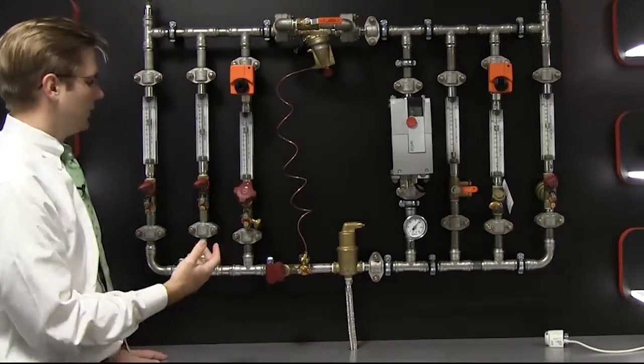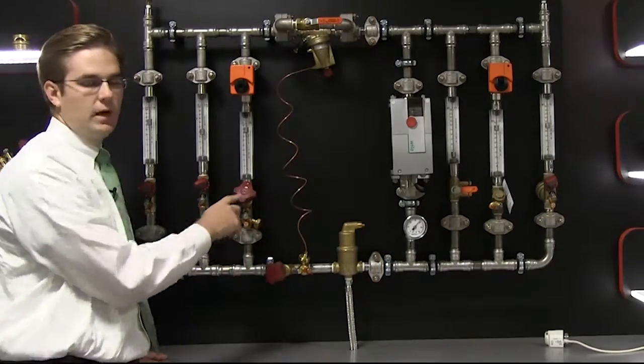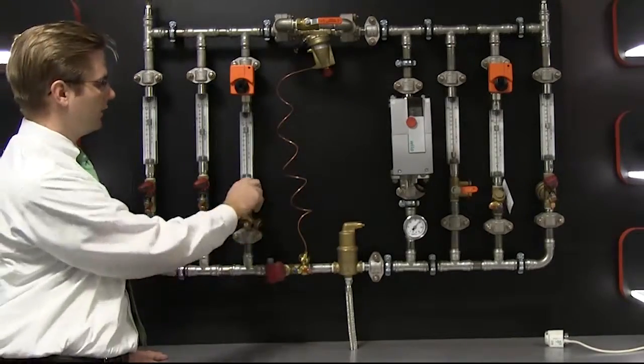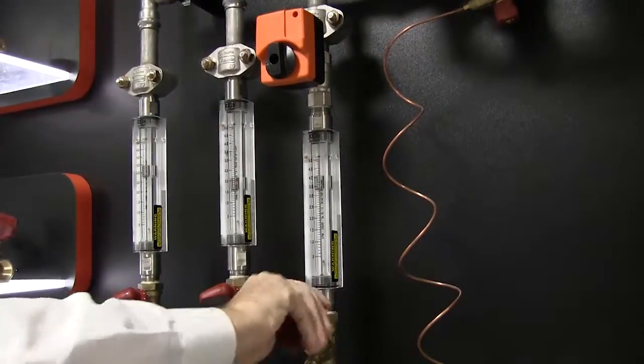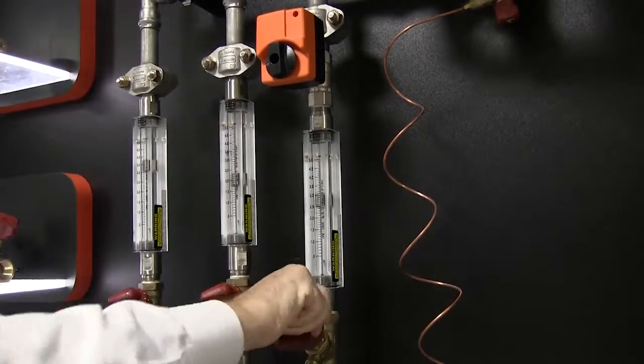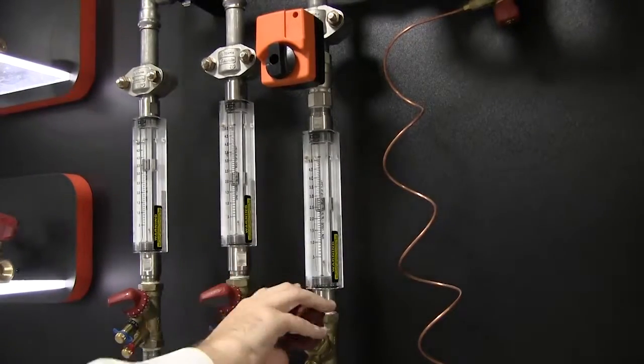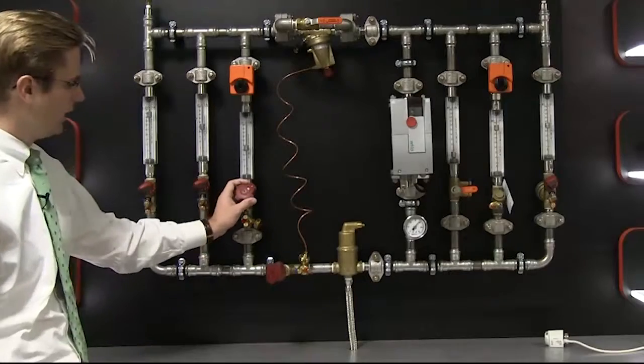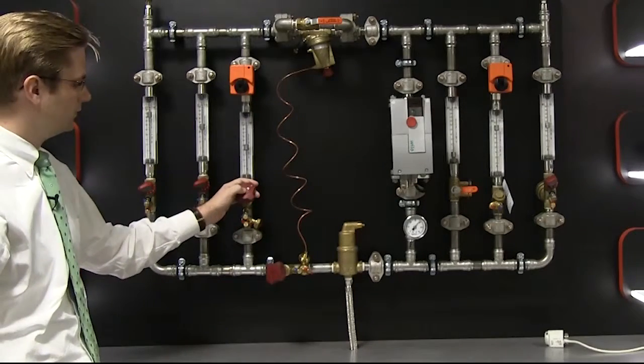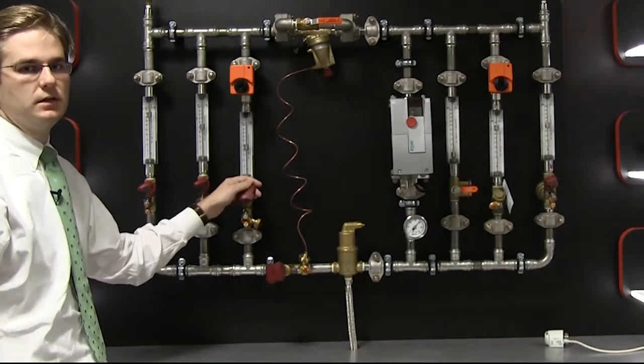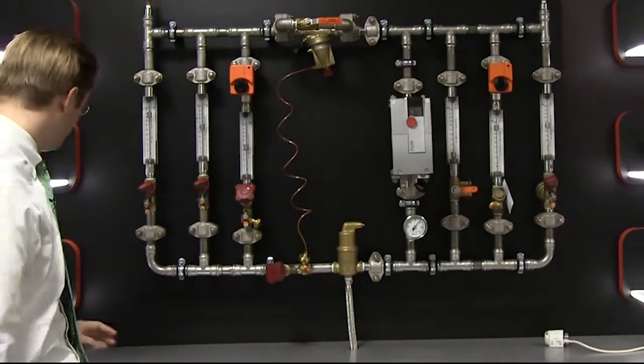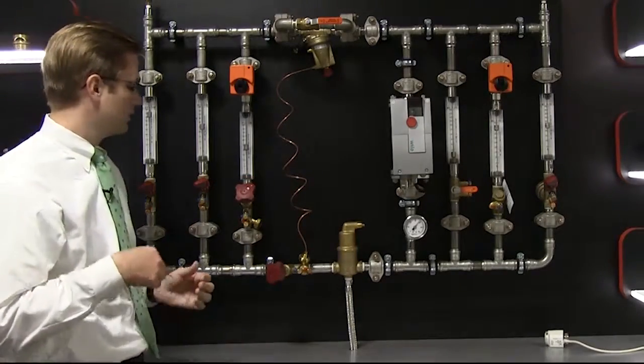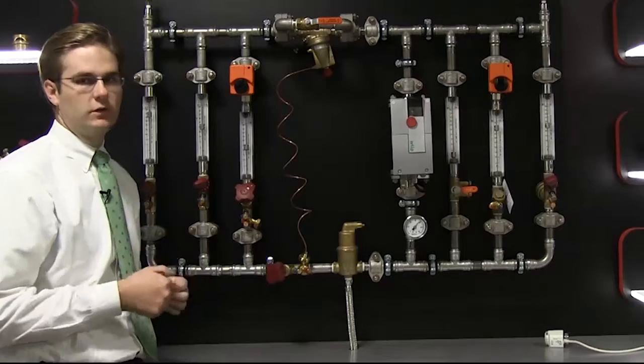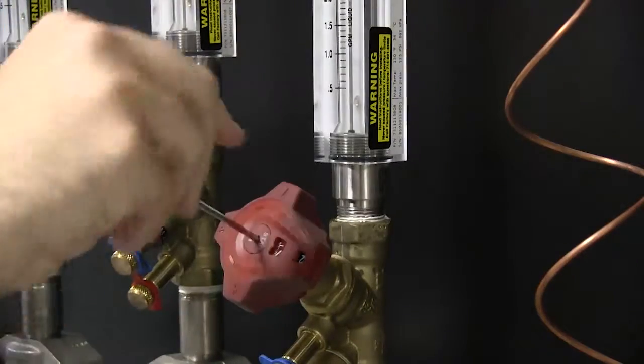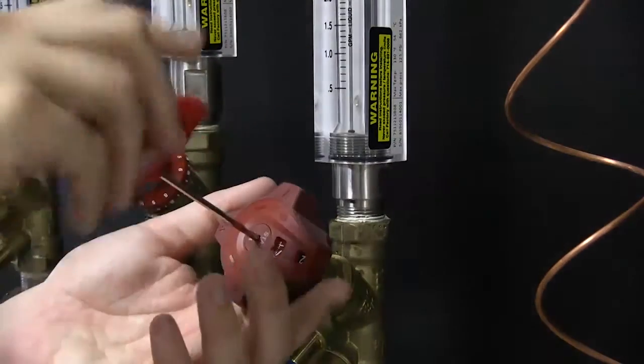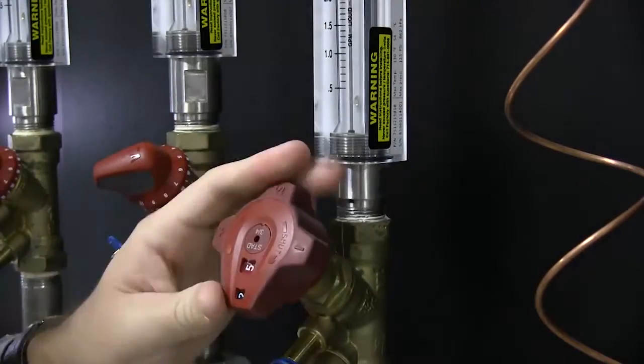On the left side, we have a manual balancing valve, which is a Y-pattern globe valve, which has 4 turns to open. You can see it's much easier to get the proper flow rate. We have a digital hand wheel setting so you can see the exact flow rate. And we even have a memory stop. So when the valve is set to the correct flow rate, you can close the memory stop and prevent the valve from being opened further than the set point.